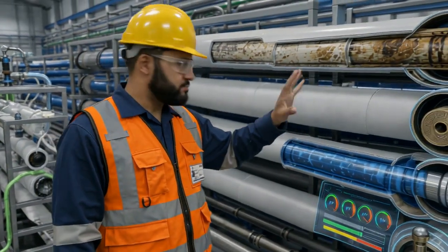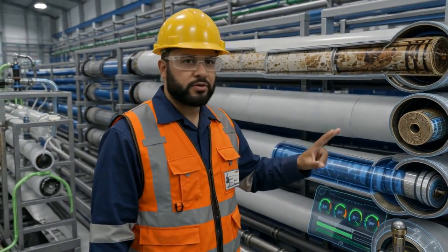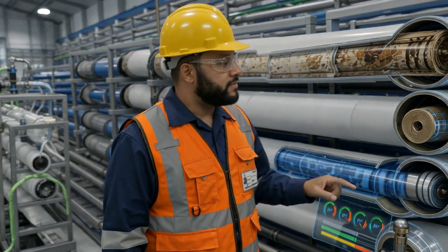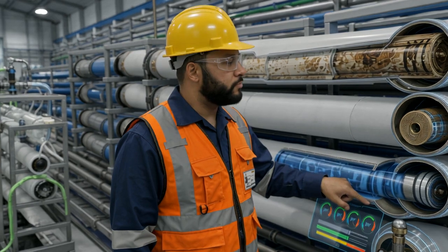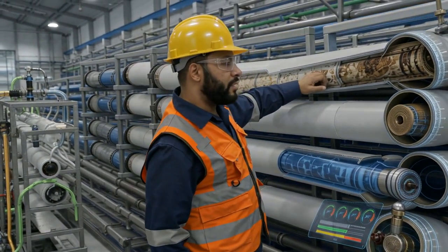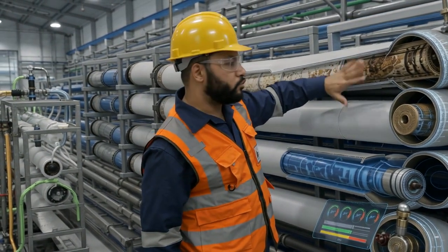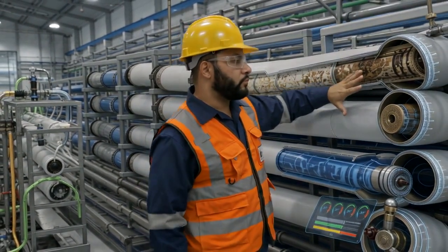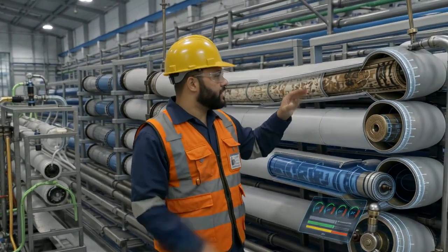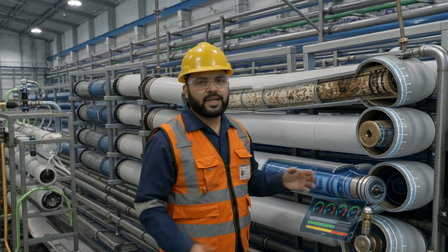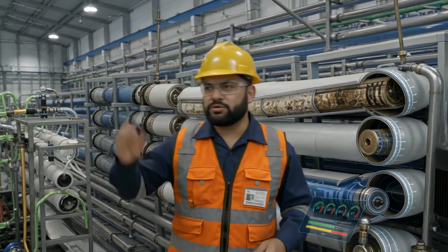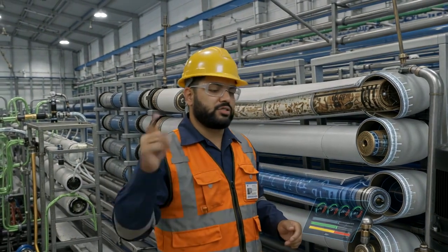The second challenge is biofouling. Microbial growth can form slime layers inside membrane elements, increasing differential pressure and reducing permeate flow. Maintaining clean pretreatment, controlling nutrients, and applying approved biocide practices where suitable help keep this under control. The third challenge is chemical degradation. Exposure to oxidizing agents, especially free chlorine, can attack the polyamide layer. Once that membrane chemistry is damaged, cleaning will not restore full rejection, and replacement is usually required.